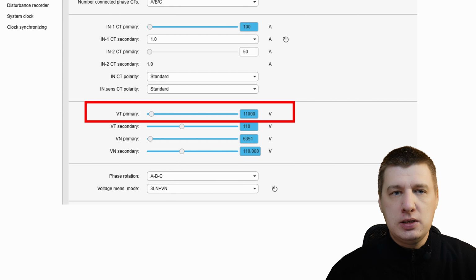The VT primary is the rated voltage on the high voltage side of your voltage transformers. Protection relays like the P5 aren't built to handle thousands of volts directly. Instead, they use VTs to step that massive voltage down to a safe, measurable level, usually around 100 or 110 volts. The VT primary setting tells the relay what that high original voltage actually is.